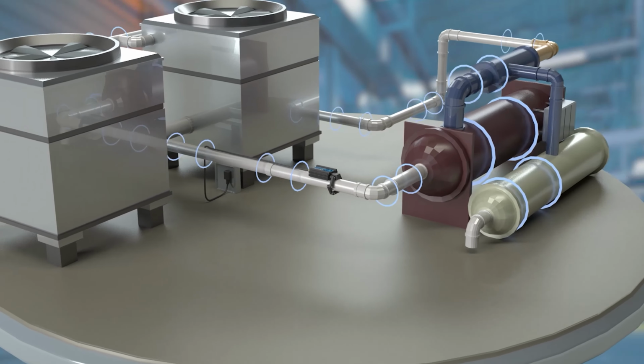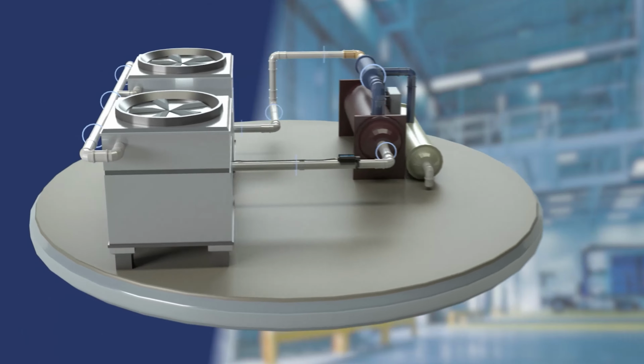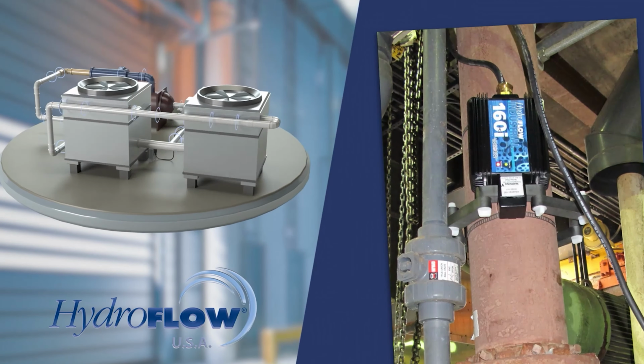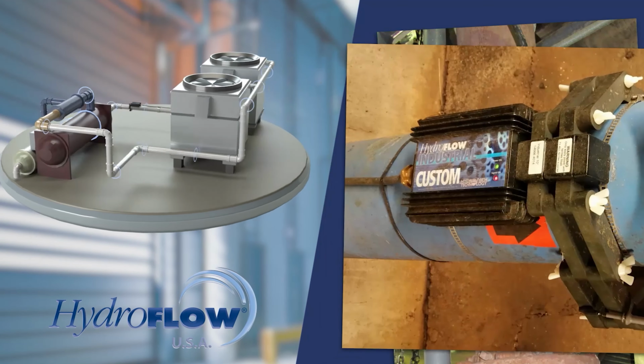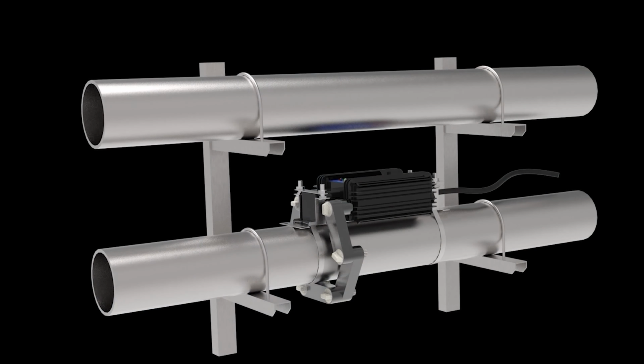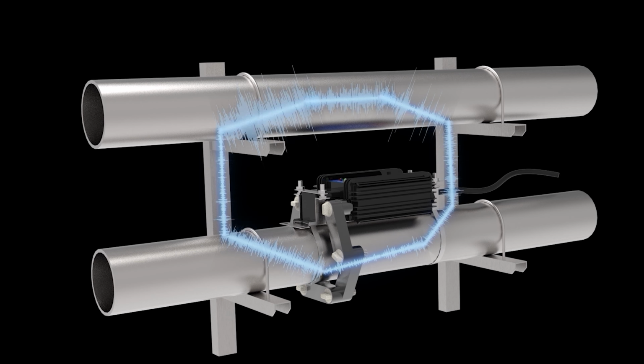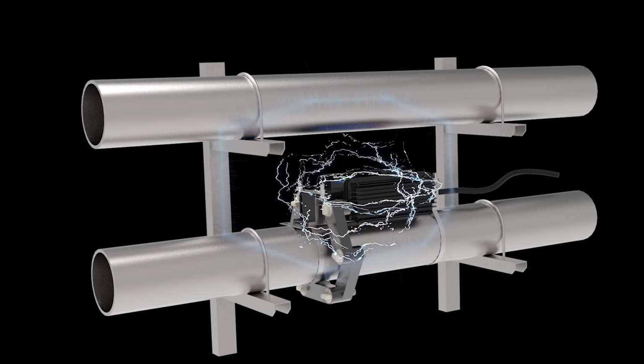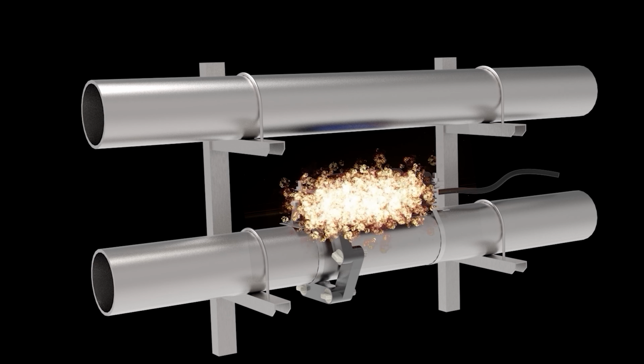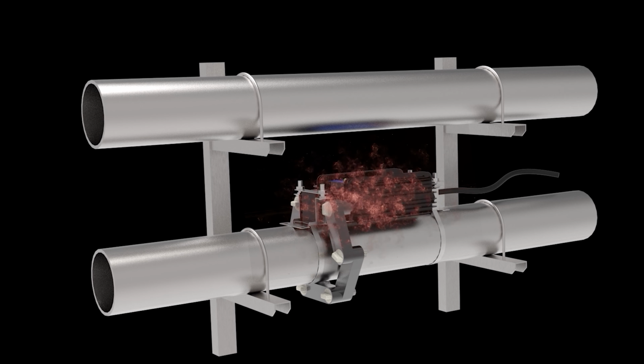If the unit is installed in what we call an electrical loop, this signal will not be able to propagate correctly and performance will be reduced. An electrical loop is caused when the HydroFLOW unit is installed in a location where there is an easy electrical path from one side of the unit to the other, a short circuit of sorts. In this situation, the electrical current does not have to travel through the entire piping system to ground, but rather has an easy path back to the other side of the unit, causing the signal to become trapped, which damages the equipment along with greatly reducing its performance.